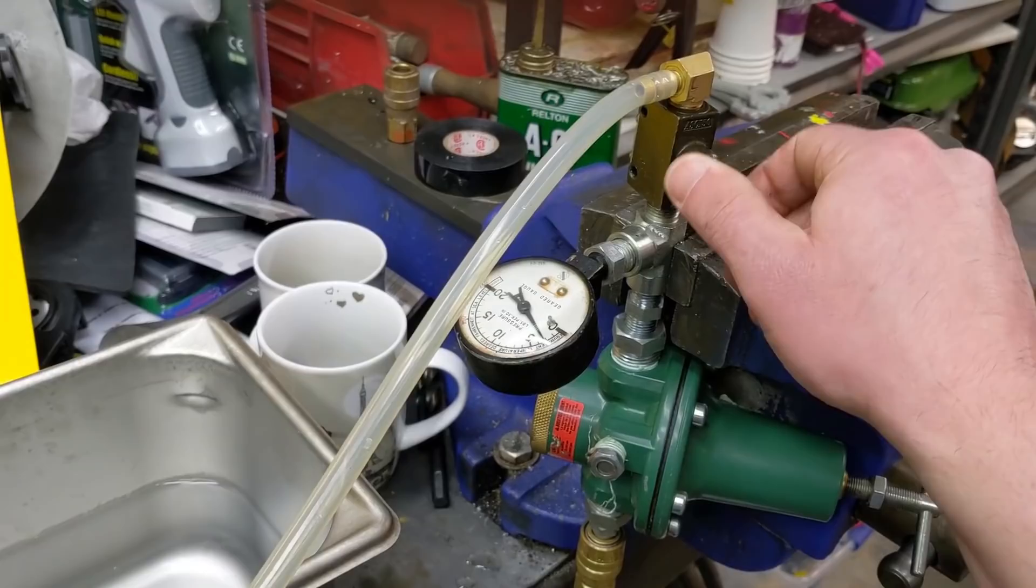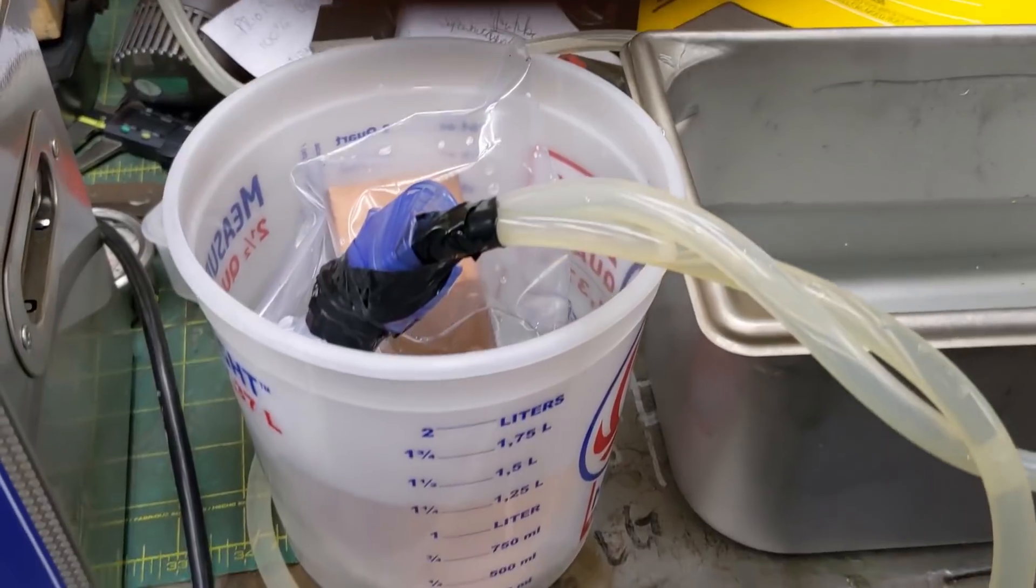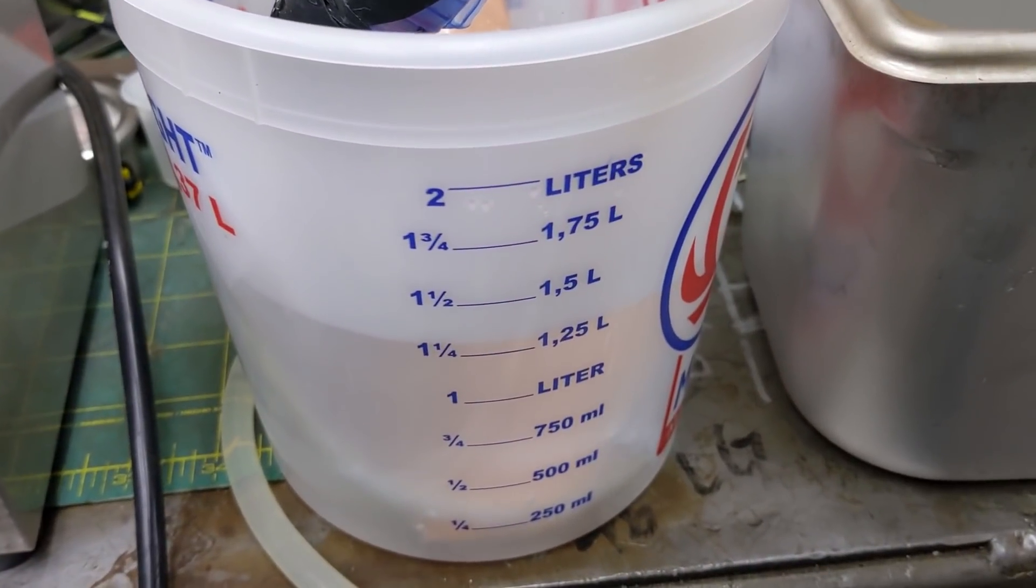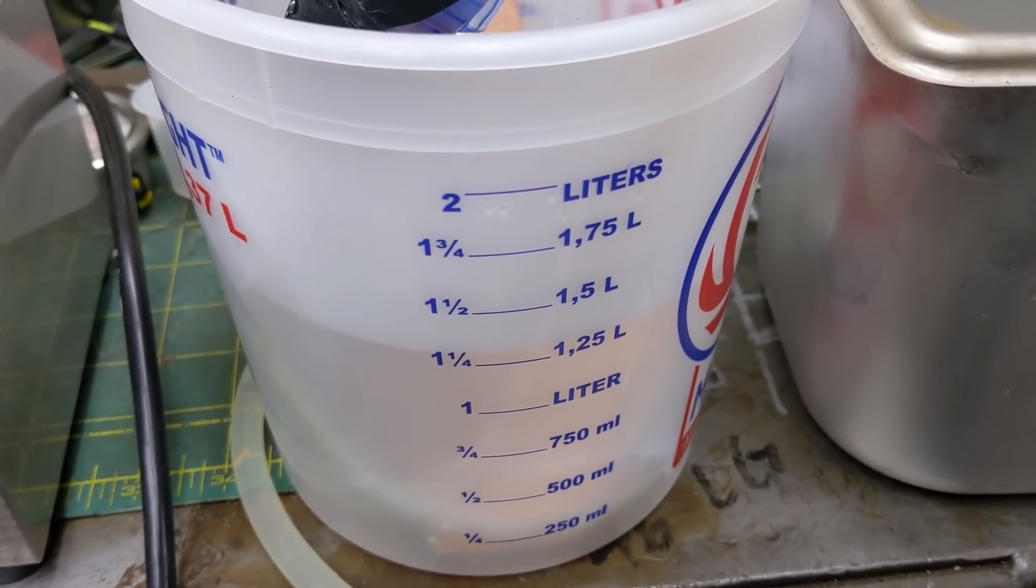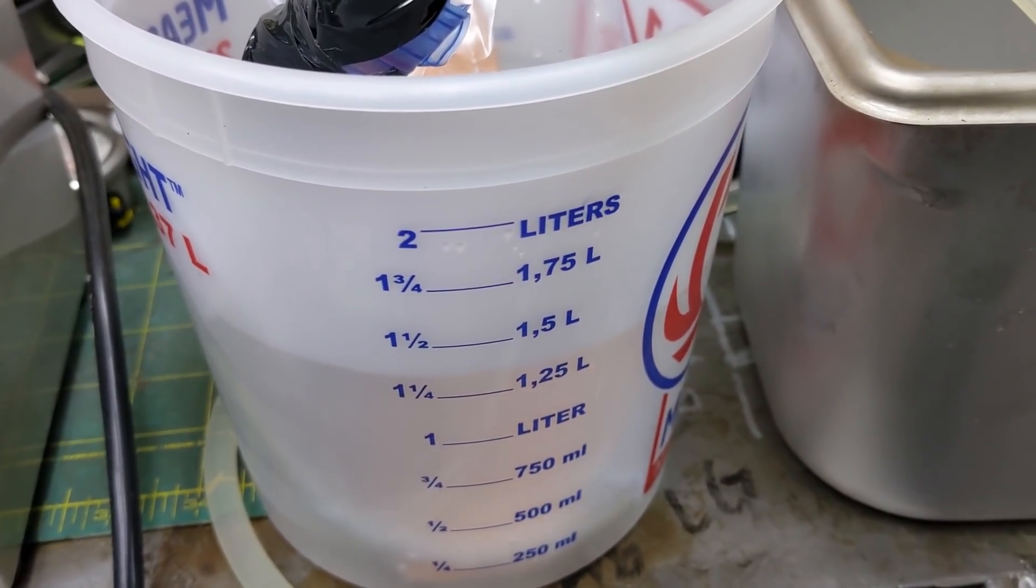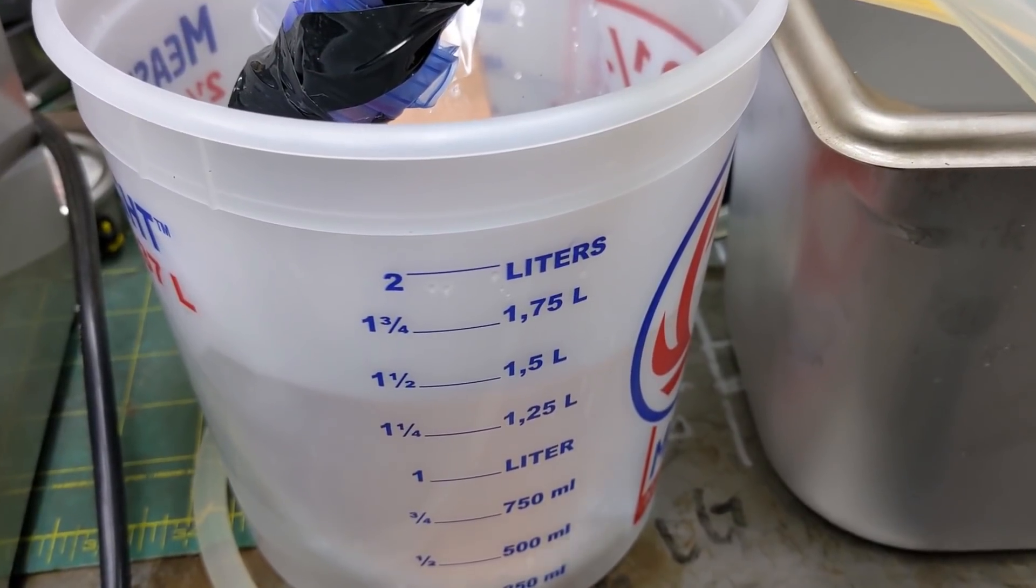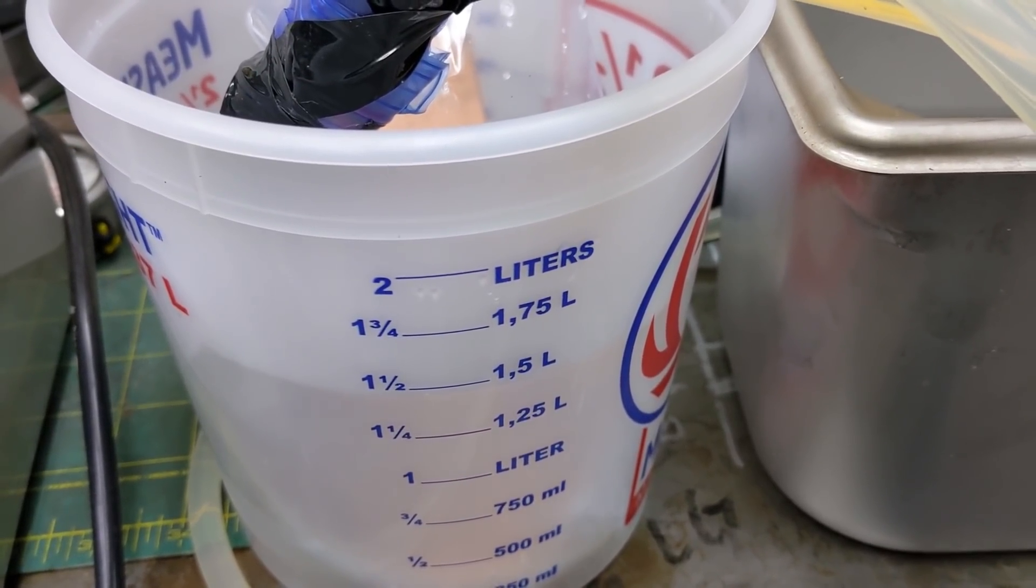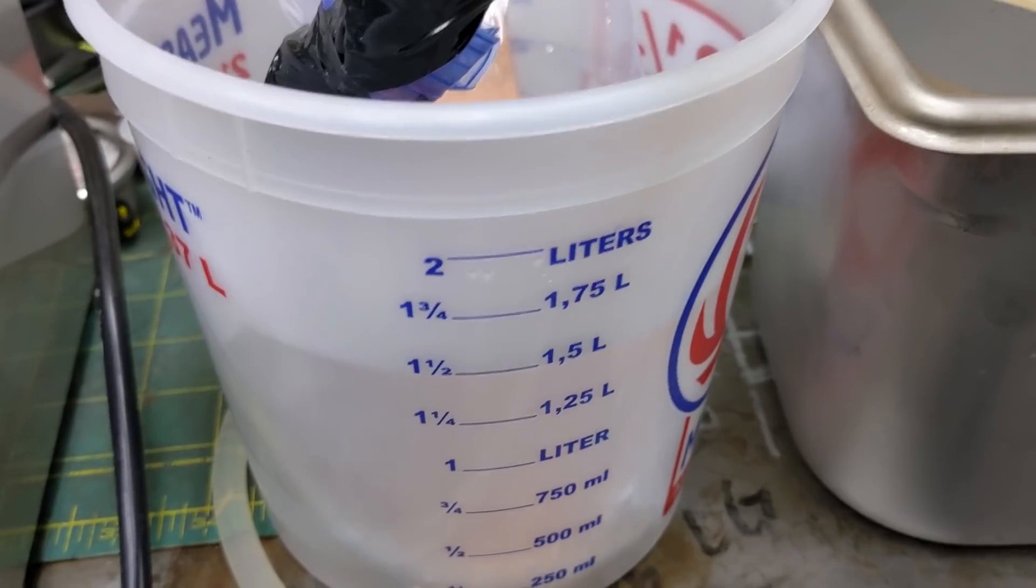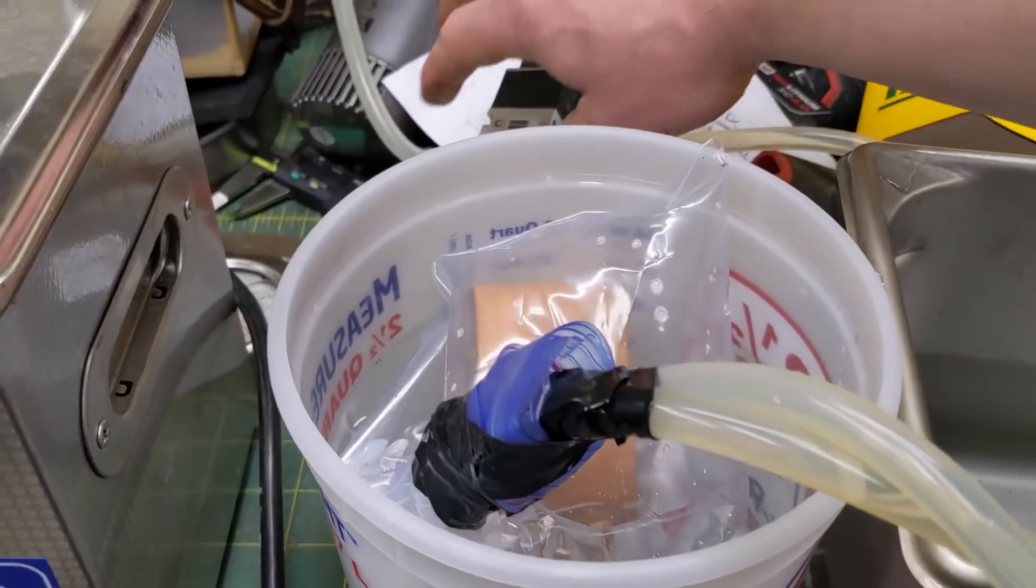And we'll just burble this in. And there we go. We will see the water rise to the desired volume. This is just a timing issue. We want, I don't know, 5, 10 breaths. You can adjust all that as well without a computer. So there we're at the level we want. Now we actuate the valve.